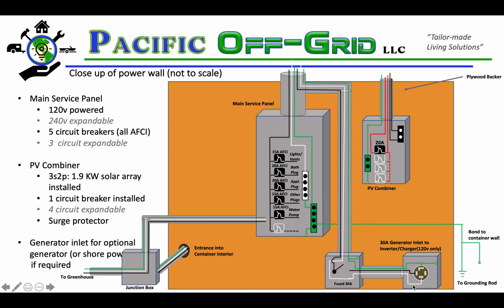Proper grounding and bonding are also fundamental parts of the safety plan of this project. The container wall will get bonded to the grounding circuit, and this will all get connected to at least one 8-foot grounding rod buried to comply with the grounding requirements in accordance with the NEC.